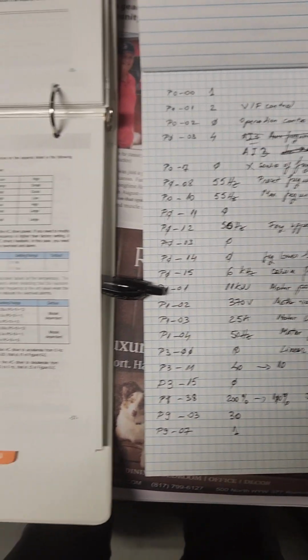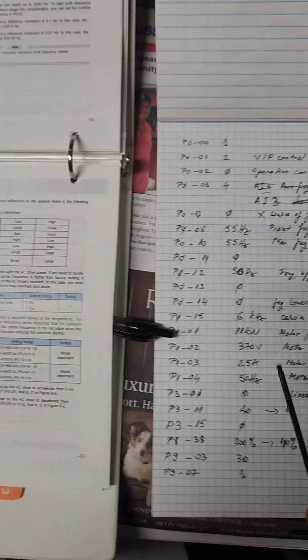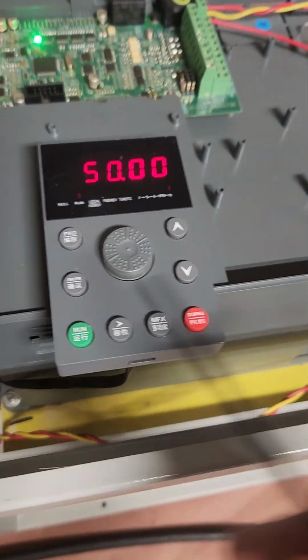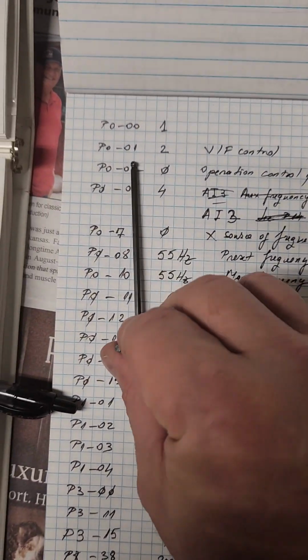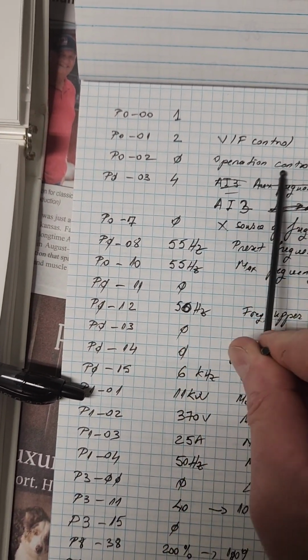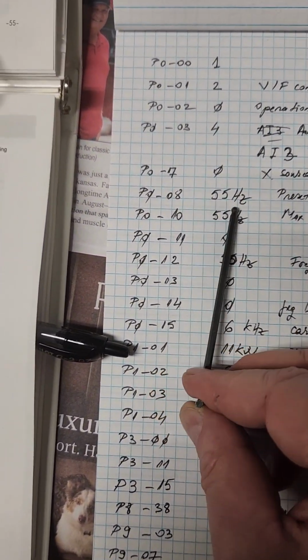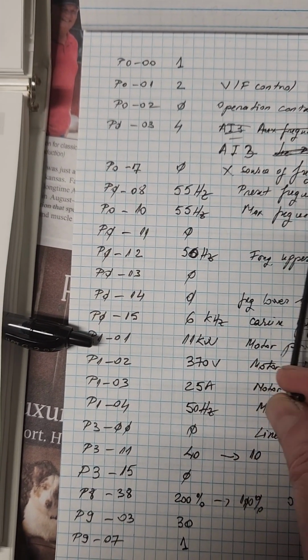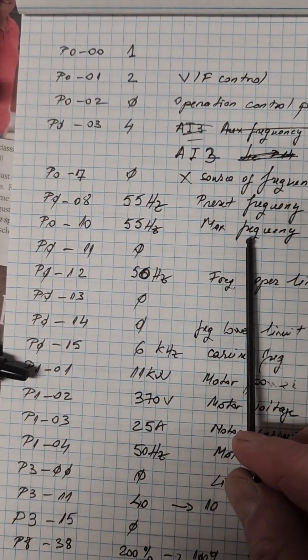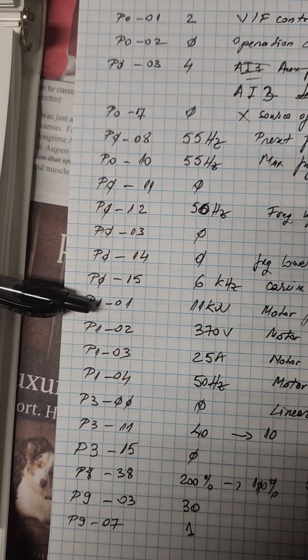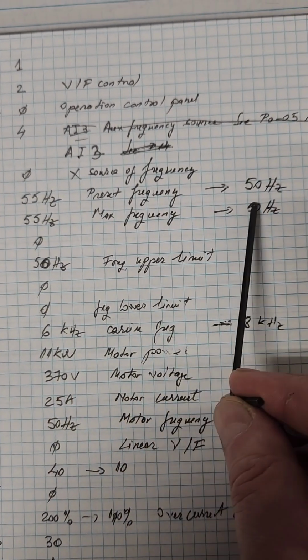I was able to find the manual for this, and I took some of the parameters out of the VFD through this control panel. You just go over the parameter and see what the values are. And I took only the one relevant for what I need here. So this is voltage frequency control. It's operated from the control panel, meaning this control panel. And it has this frequency, preset frequency. That's the frequency you would run when you started, and you adjust this here, right? And then it has also the max frequency you would be able to set it, and frequency upper limit was at 50 Hertz.